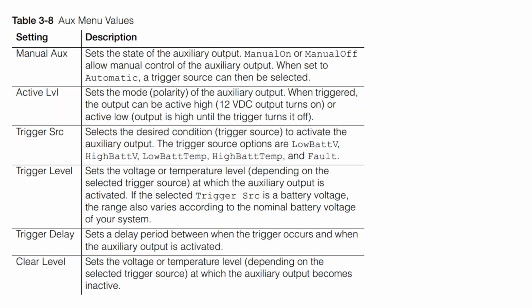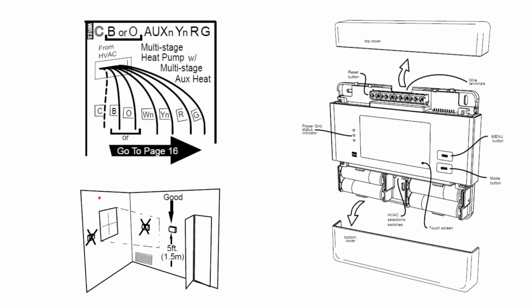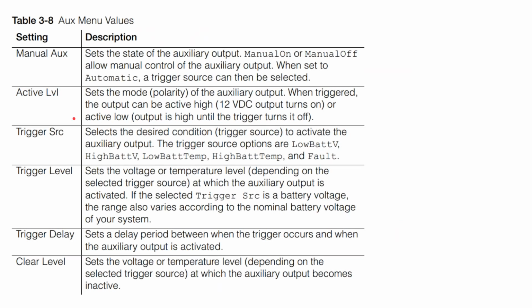There are some functions built into battery inverters to help with energy management. You have auxiliary circuits and trigger levels that will fire up circuits when the battery is at a low state of charge, such as a generator auto-start, or that will shed service panels at a certain state of charge, or turn on circuits when the battery's at a full state of charge. So it's not a bad idea to use an auxiliary output and trigger feature in the home, like a water fountain out in the yard, so that when the fountain is bubbling, it means your batteries are at a full state of charge and your home has healthy battery life.